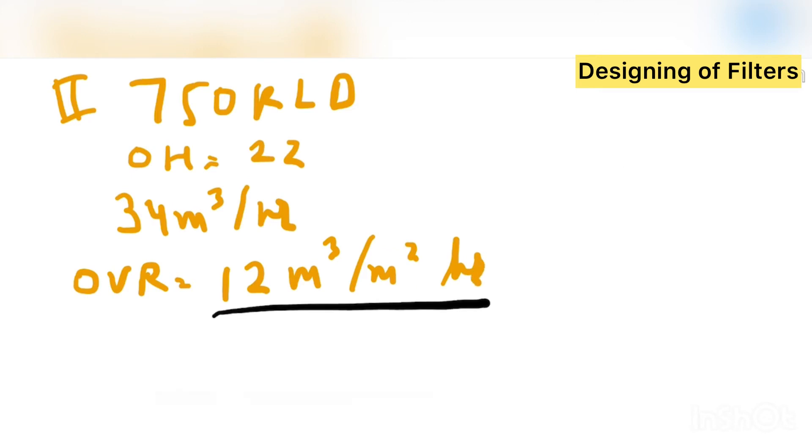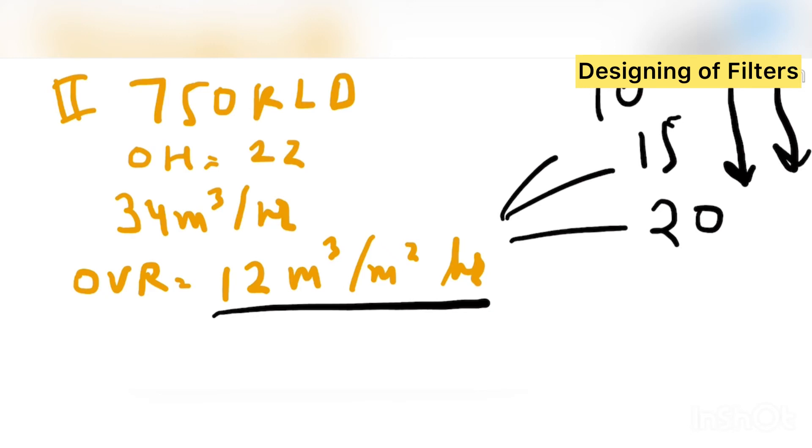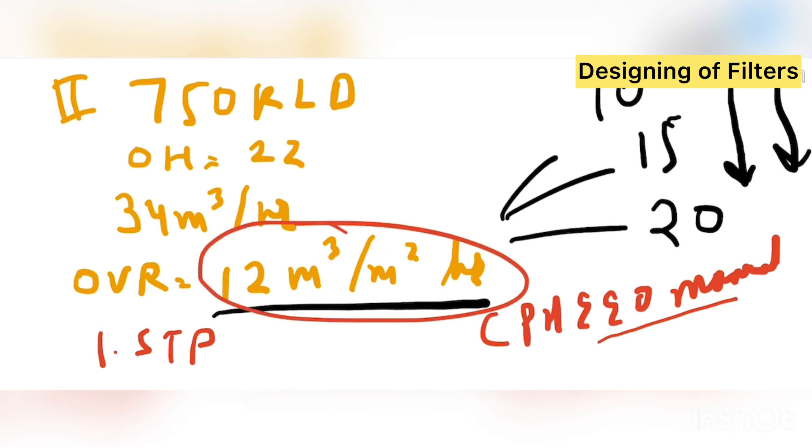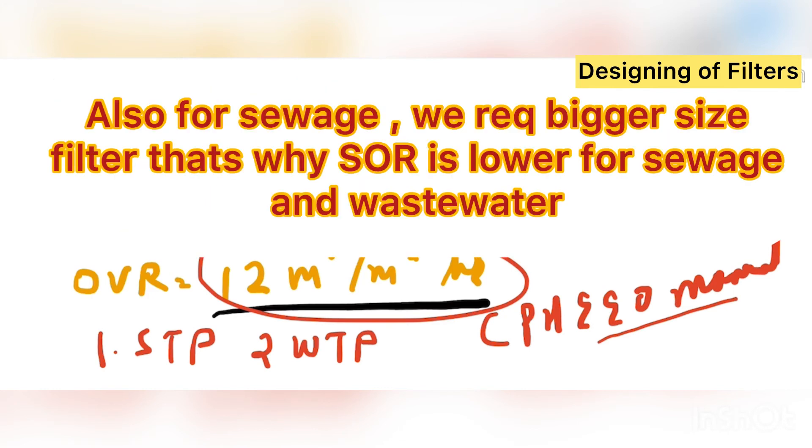So you want to know why I have considered this 12 only. I can consider 10 also, I can consider 15 also, I can consider 20. If you see, the higher I go, the diameter will also decrease. If I consider lesser value, the diameter will increase. So why we are choosing 12? Because in CPHEEO manual they have suggested, if the water is from STP, sewage treatment plant, then we have to consider this. But if the water is from WTP, water treatment, then we can take this value like 20 or 22. Then our diameter will be of lesser size.